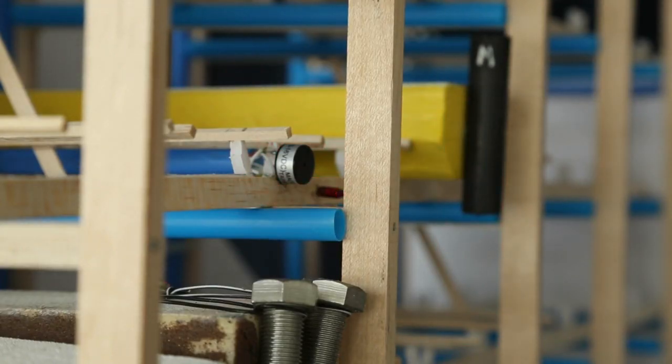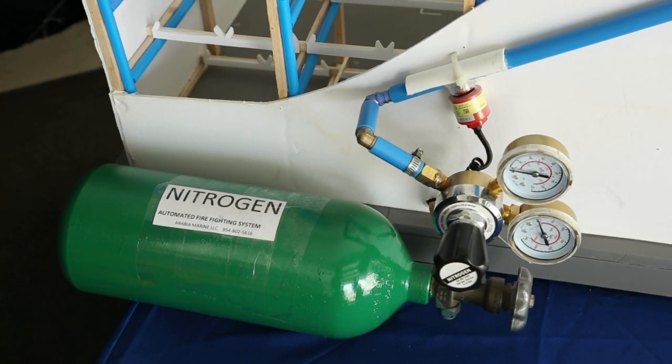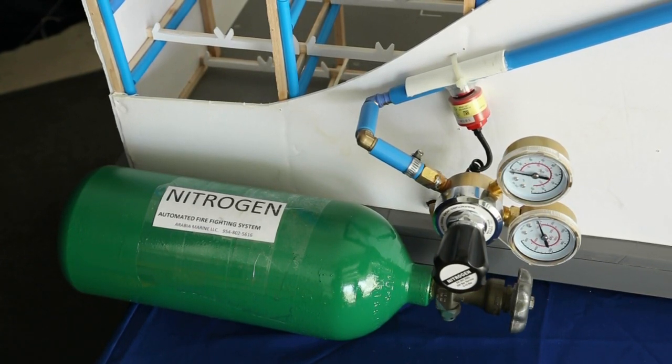The nitrogen system requires the use of sophisticated fire alarm systems with smoke, heat, and CO2 detectors adjacent to the potential fire development areas of all boats. The nitrogen gas will be stored at pressure in a container outside the warehouse.